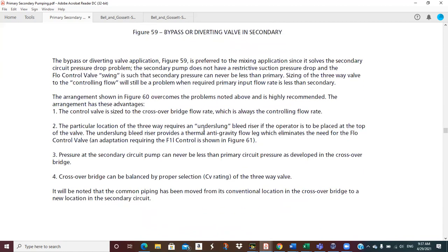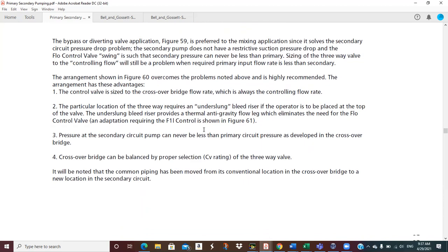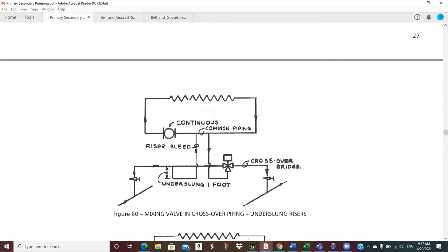The arrangement shown in figure 60 overcomes problems and is highly recommended. Arrangement has these advantages. Okay, control valve is sized to the crossover bridge flow rate, which is always the controlling flow rate. So say this is the flow rate that you have to control, the primary water that's going through the crossover bridge. Well, if it's a cooling application, then this flow rate and what you're circulating up here is probably going to be the same, and this is not so critical.